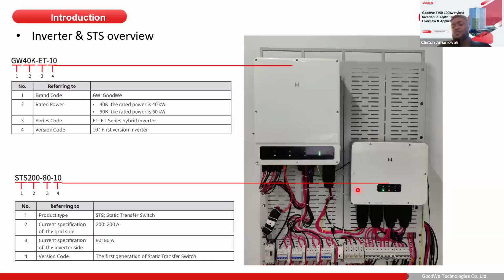This STS unit comes with four AC connection ports, and also LED buttons here, where it speaks to the installer as well. With this, you are able to understand whether your system is working in on-grid mode or off-grid mode, as well as whether there is communication established between the STS unit and the ET inverter. There is also a fourth LED that tells you whether there is an abnormality or the system is working fine.